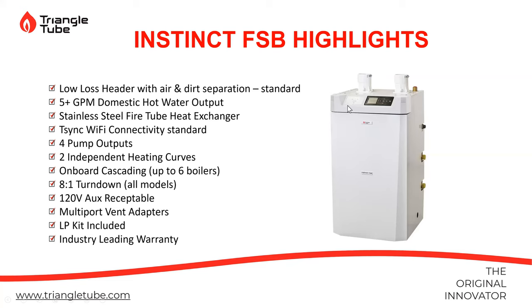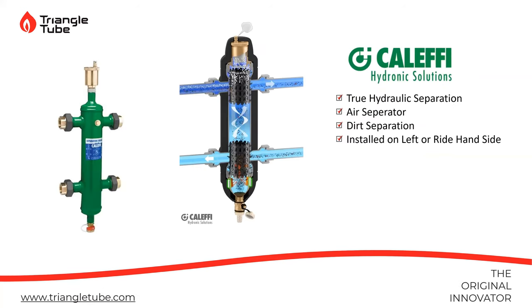Another thing I'll show you on this is the boiler right here next to the control has a Wi-Fi control. So we'll go through some of that. I'll show you my boiler at my house, and you can get an understanding of how that looks and what you can actually expect out of that Wi-Fi controller. And this is the low loss header that we sent to it. I think that's a 548 or 545? Pretty basic. The only thing this doesn't have, which I kind of wish they put on there, but I think it was a cost thing, was the magnetic separation. So if you go into a system where you have cast iron radiators or you're concerned about metal particles, I would definitely add a magnetic separator on there.